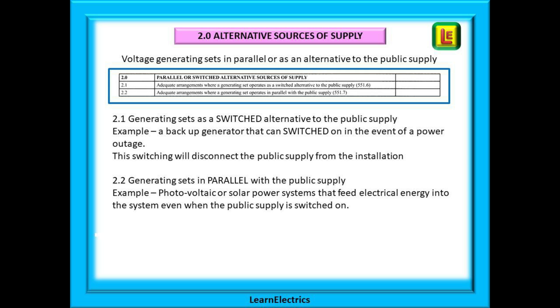Section 2 is about voltage generating sets that are in parallel to, or as an alternative to, the public supply. Item 2.1 is for generating sets that are a switched alternative to the public supply — we cannot have both on at the same time. An example would be a backup generator that can be switched on in the event of a power outage. Item 2.2 is for generating sets that are in parallel with the public supply — for example, photovoltaic cells or solar power systems that feed electrical energy into the system even when the public supply is switched on.